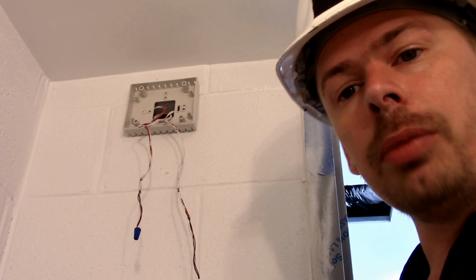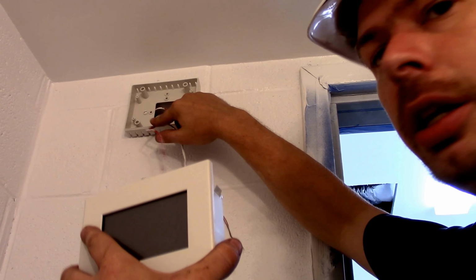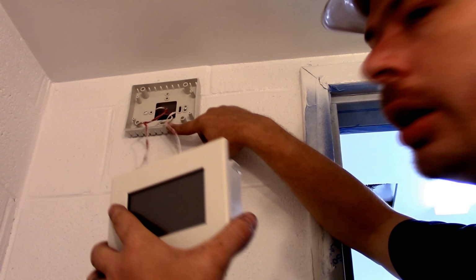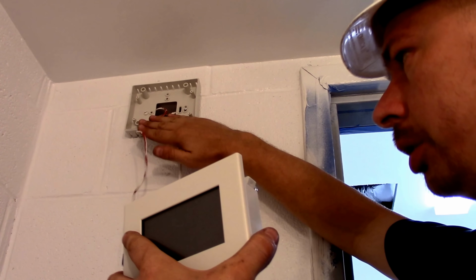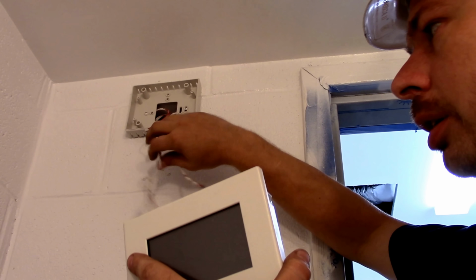So we're mounting this, and it's really sensitive to radio wave frequencies on the thermostat wires, so they use shielded internal wire with ground to protect it from any kind of problem. So this will work, but it would be preferred to have 18/8 and a shielded wire - that combination is better.